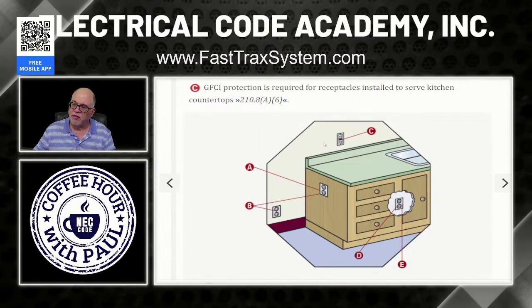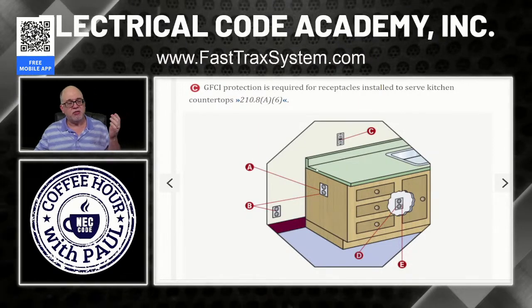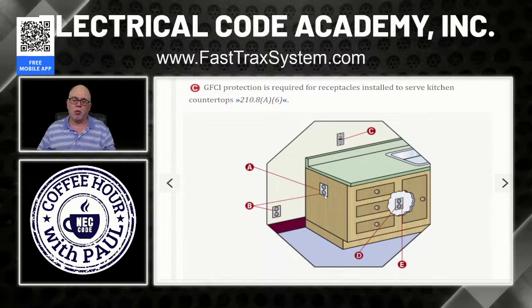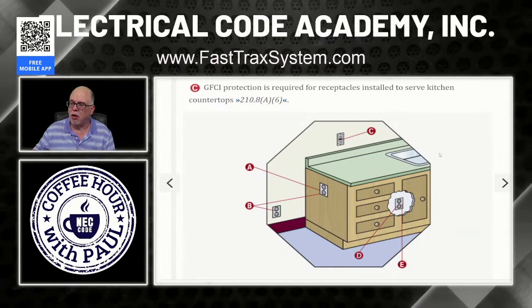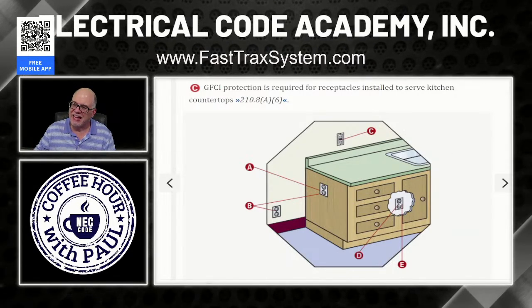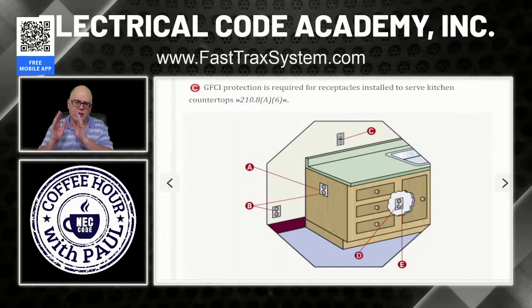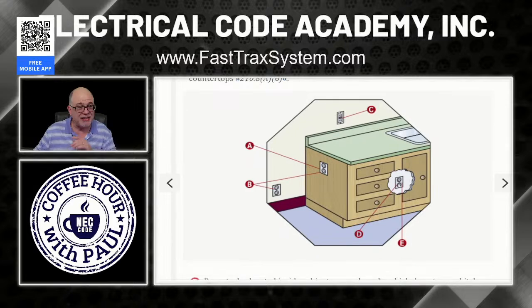Obviously, if this is to serve the countertop, then it would be GFCI protected. But say it wasn't to serve the countertop, if it still was within 6 feet of the top inside edge of the sink or bowl, it still would require GFCI protection, right? Now, what about these that are inside the cabinet, maybe for the garbage disposer, or maybe a dishwasher, maybe you're using a plug and cord application for that? Well, let's look at these receptacles inside of the cabinet.